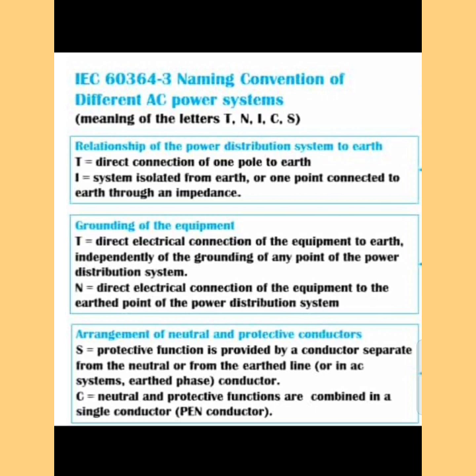Apart from that, sometimes a third letter is present that describes the arrangement of the neutral and protective conductor. S means the protective function is provided by conductors separate from the neutral or from the earth line. C means neutral and protective functions are combined in a single conductor, called the Protective Earth Neutral conductor — PEN.